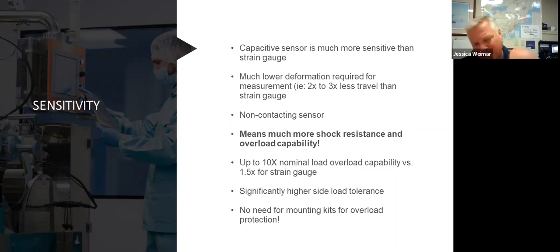Where is this important? Think about something. In our business, we've got a lot of clients that have mobile weighing or mobile carts. In the pharma business, let's say you have a cart that has got a disposable bag in it. You want to measure the liquid volume in that disposable bag. The challenge is you can't use conventional methods to measure the liquid volume because the bag is irregularly shaped. So they use weight. Provided you know the specific gravity of the liquid, you can calculate the volume of the liquid that's in there.